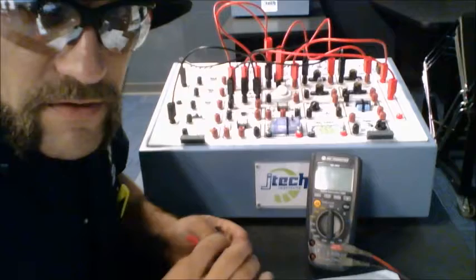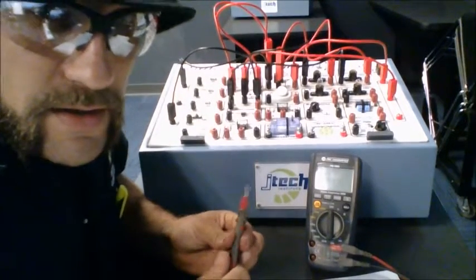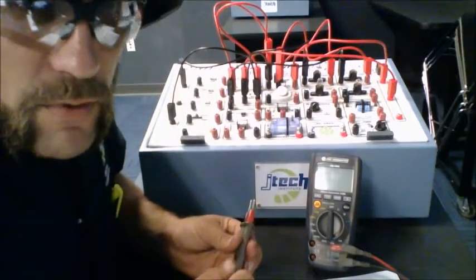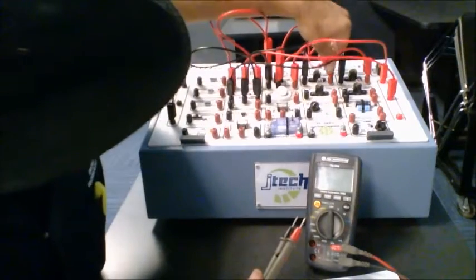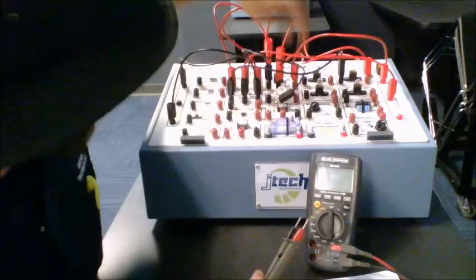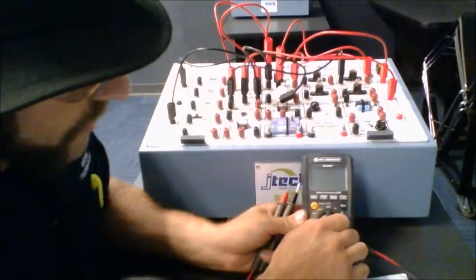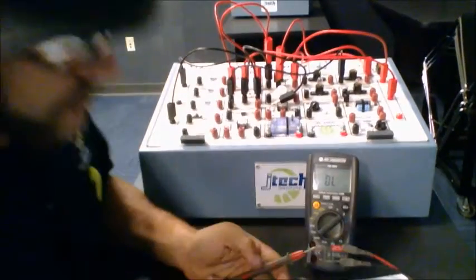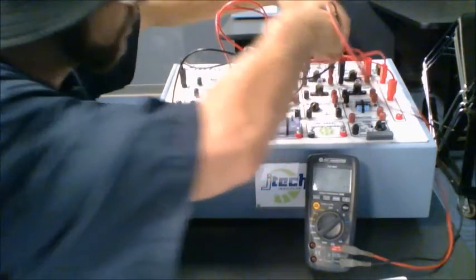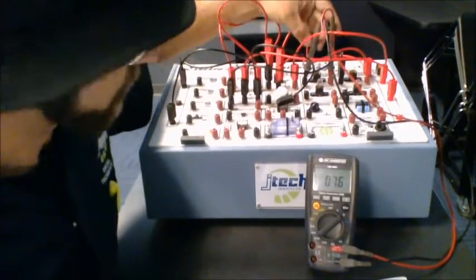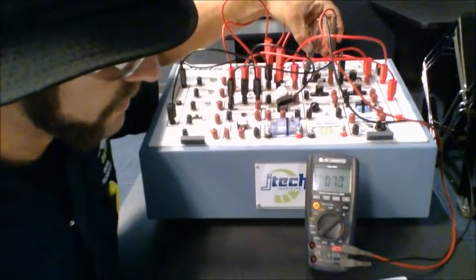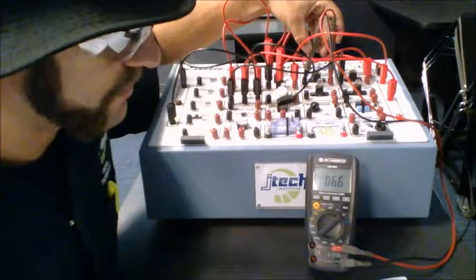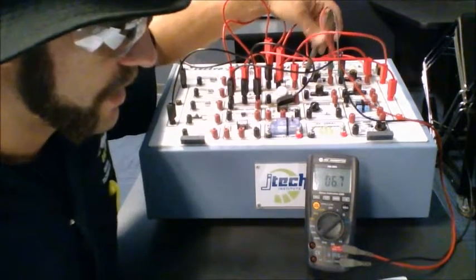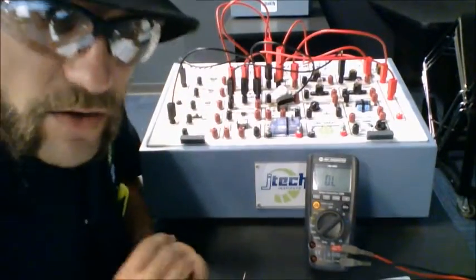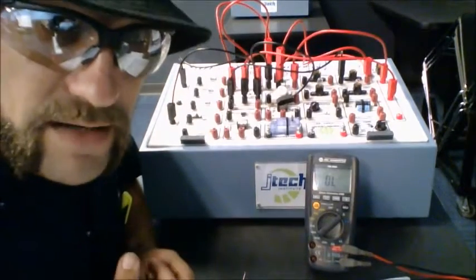Next, I'm going to be showing you how to check for resistance. You want to check for resistance to ensure a component is not providing too much resistance, which could short power out. In order to check for resistance, the component needs to be isolated and shut off or completely disconnected from the system. You'll set up your multimeter into ohms. Alright, we already know that we have a 0.6 ohm on this particular multimeter, and you'll just connect your leads to both ends of the component, and you will make sure you have good contact, and you will take the measurement of the ohms. Once it balances out, you'll see that we have a 6.6 ohm reading, and we know that this has 0.6, so it's a total of 6 ohms on that component, which you would then compare with a spec list and make sure it's within tolerance.